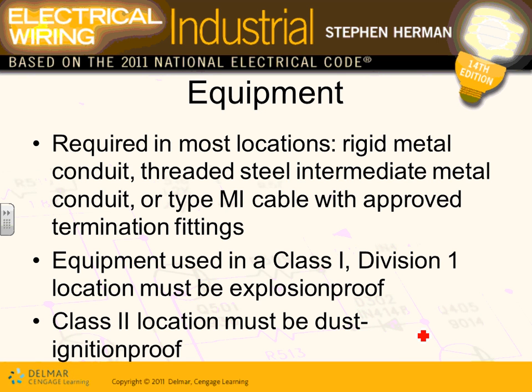Okay, equipment. If you put equipment in a hazardous location, most of the wiring methods have to be rigid metal conduit, threaded steel, intermediate metal conduit, or MI cable. So in a hazardous location, Adam, Class 1, Div 1 and 2, can you use EMT conduit? No. MC cable? No. AC cable? No. You have to use special wiring methods, the most robust ones, which is rigid, thick steel conduit, threaded, so the gas cannot get into them. You can thread them really well. Or MI cable, which is one of the most robust cables. Any comments, guys? Any question why it's so important to know the place that you're in, the hazardous location? You have to use different wiring methods.